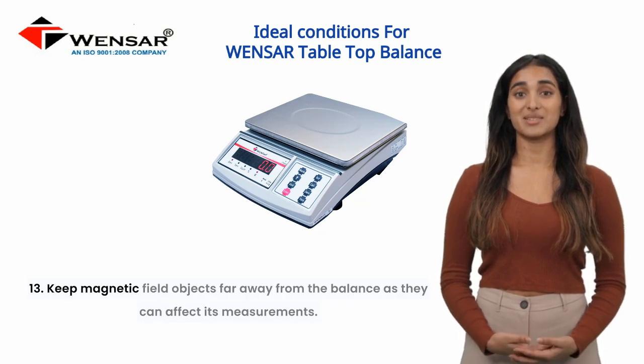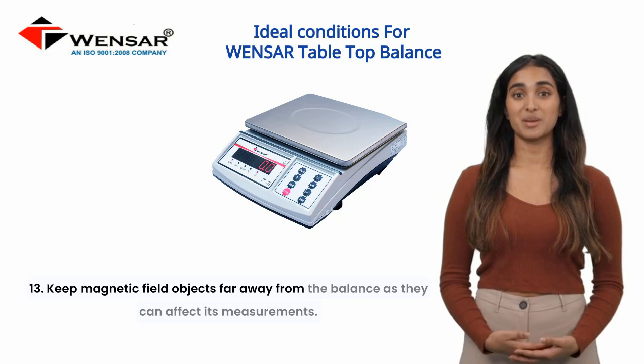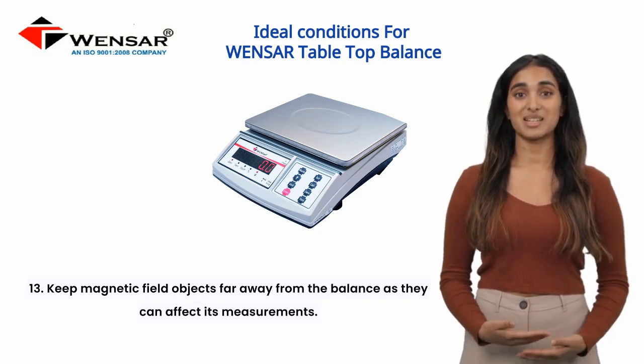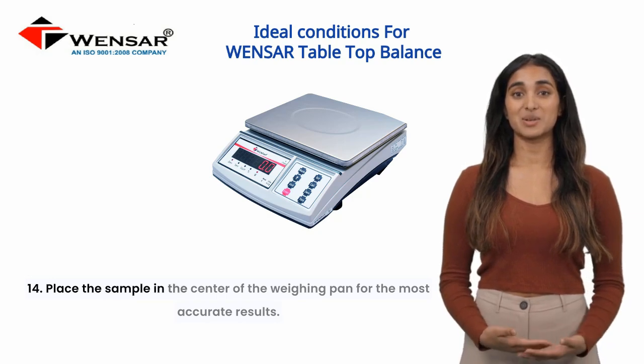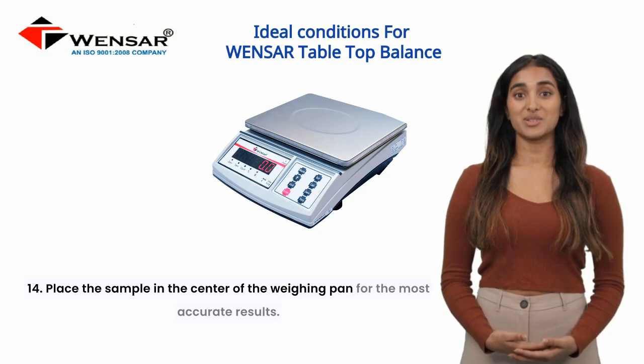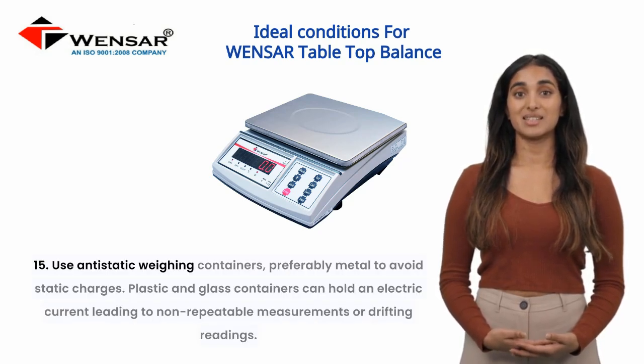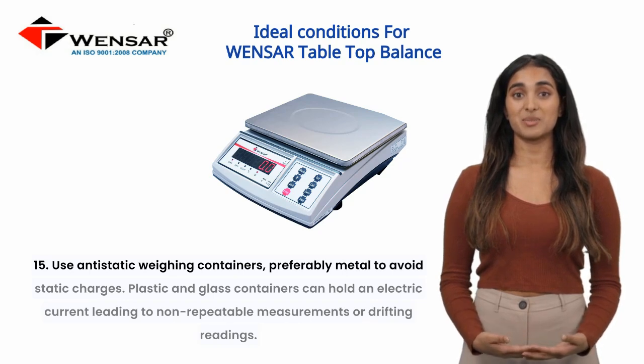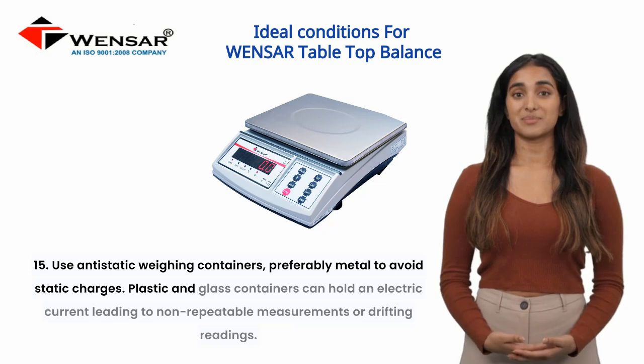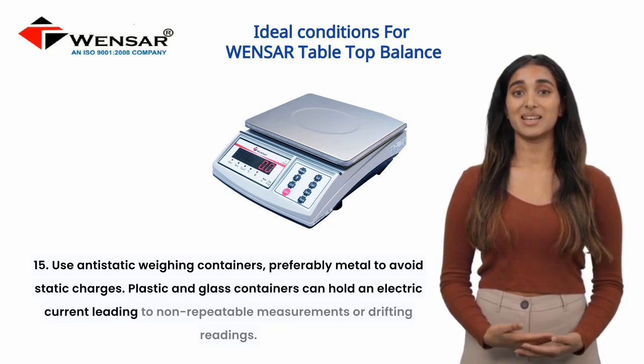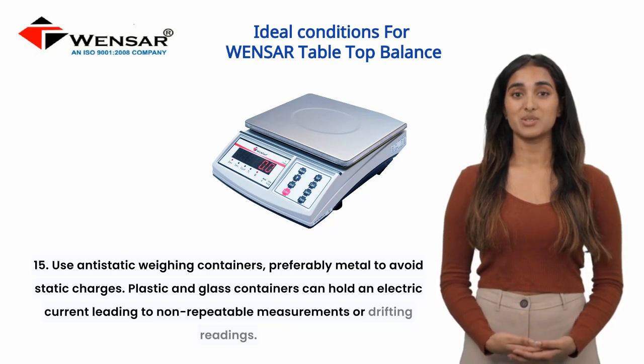13. Keep magnetic field objects far away from the balance, as they can affect its measurements. 14. Place the sample in the center of the weighing pan for the most accurate results. 15. Use anti-static weighing containers, preferably metal, to avoid static charges. Plastic and glass containers can hold an electric current, leading to non-repeatable measurements or drifting readings.